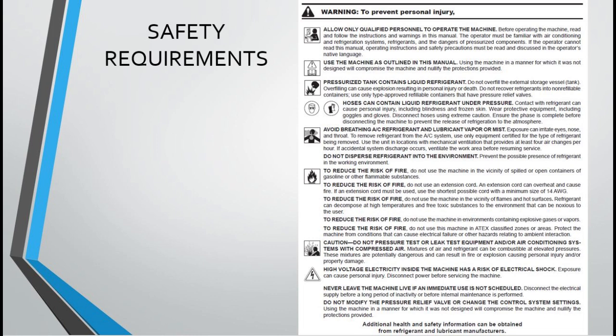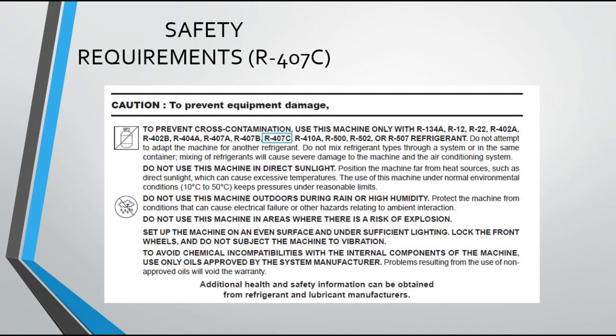Caution, do not pressure test or leak test equipment and/or air conditioning systems with compressed air. High voltage electricity inside the machine has a risk of electrical shock. Do not modify the pressure relief valve or change the control system settings. Using the machine in a manner for which it was not designed will compromise the machine and nullify the protections provided. To prevent cross-contamination, use this machine only with R407C.